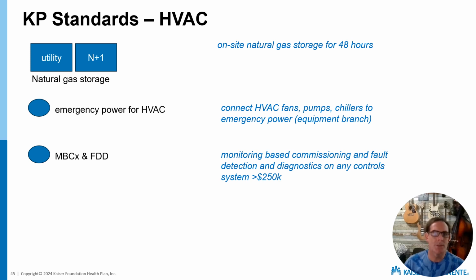The top requirement on this slide is actually a code requirement: natural gas storage for 48 hours. That's for the generators. The Kaiser standard is to connect the HVAC fans and the pumps and the chillers to the equipment branch of the generator. That is not to say that we can run those things from our emergency generator or that we've sized the generators with full capacity for that. That is just to say that we are going to connect them to the equipment branch so that we have the option to do load shedding and move things over into HVAC if necessary.